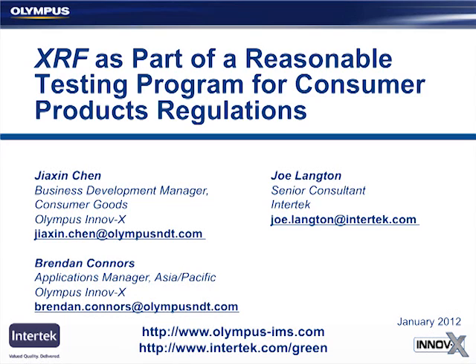The question about packaging material, how do you test packaging material for scanning? This is another restricted substances regulation that we didn't talk about. There are packaging directives in Europe where the sum of elements, chromium, mercury, lead, and cadmium have to be less than 100 ppm. One of the most difficult things with packaging materials is that your samples are really thin. So I mentioned earlier that there's a recommendation for plastics. Your samples should be at least 5 millimeters thick, and in a lot of cases you want to try to go even thicker than that if you can.